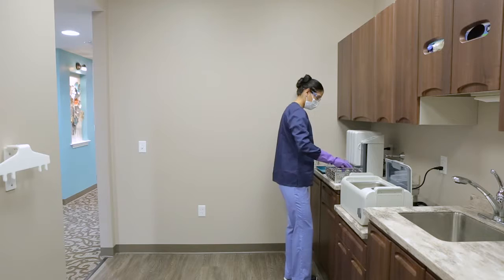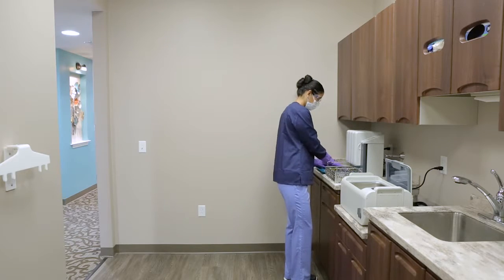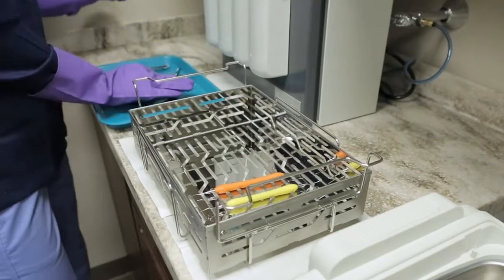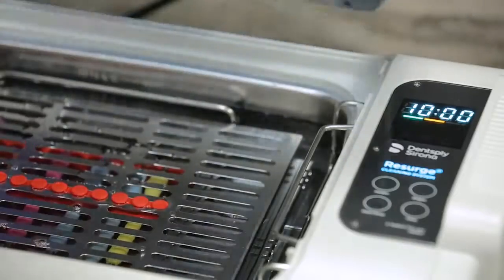Once the timer counts to zero, you are ready to start cleaning instruments. The Resurge ultrasonic cleaners use a universal rack system that allows the loading of instruments into a deep instrument basket, stackable trays, or into a variety of standard instrument cassettes.